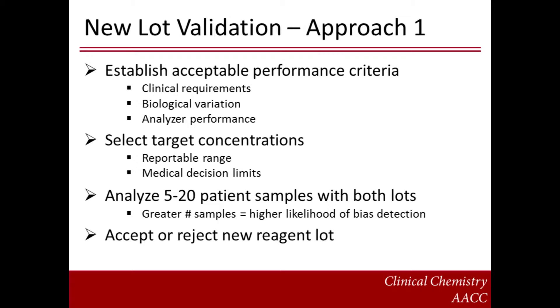A typical procedure for validating a new reagent lot in a laboratory involves comparing results for a group of patient samples using both the old and new reagent lots. The first step in this procedure is to establish acceptable performance criteria for the new reagent lot. Most laboratories will define a maximum percent difference compared to the old lot that is based on clinical considerations. For a test with a single, well-defined clinical application, this is relatively straightforward. BNP is a good example of such a test. However, for a test used for a variety of different purposes, such as HCG, the selection of an appropriate performance goal is more complex, and additional considerations including biological variation, professional recommendations, and the analyzer's analytical capabilities may be taken into account.